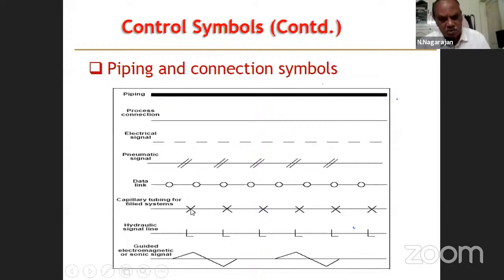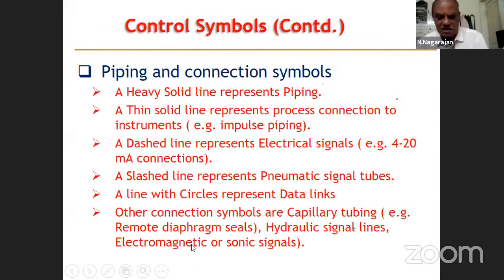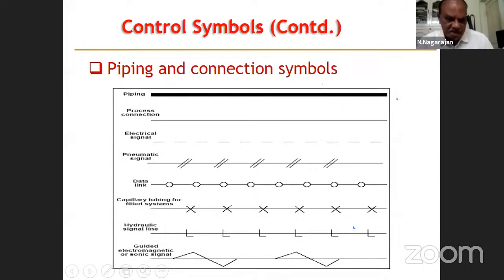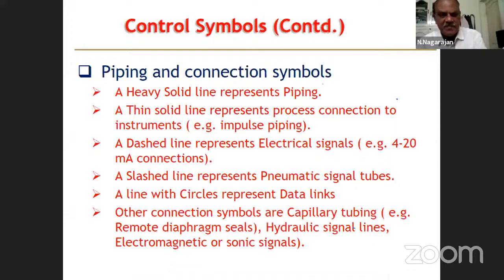Capillary tubing is used by instrumentation for connecting the transmitter and controller. This is called the capillary tubing for filled systems. Inside you have some fluid, either hydraulic fluid or air, instrument air. Then hydraulic signal means the same type of thing, but here the actuating fluid is a high pressure oil, that is called a hydraulic system. And guided electromagnetic or sonic signal. So when something is operated with the sound waves, it is called sonic, and the symbol is like this.